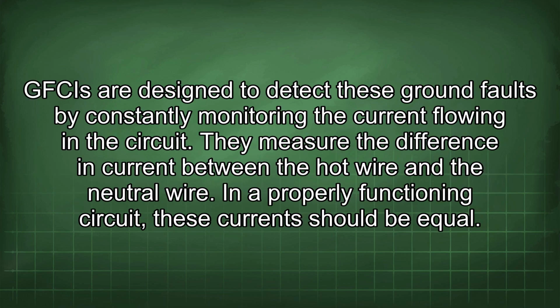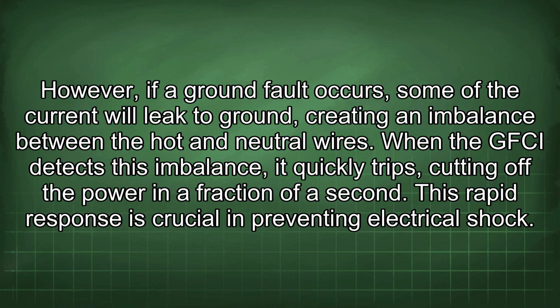GFCIs are designed to detect these ground faults by constantly monitoring the current flowing in the circuit. They measure the difference in current between the hot wire and the neutral wire. In a properly functioning circuit, these currents should be equal. However, if a ground fault occurs, some of the current will leak to ground, creating an imbalance between the hot and neutral wires. When the GFCI detects this imbalance, it quickly trips, cutting off the power in a fraction of a second. This rapid response is crucial in preventing electrical shock.